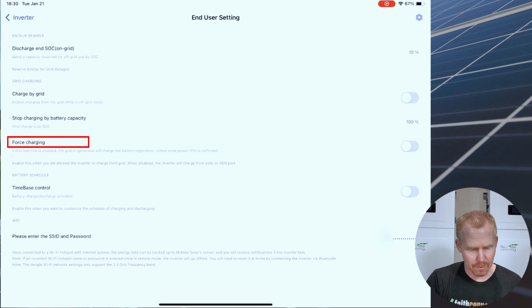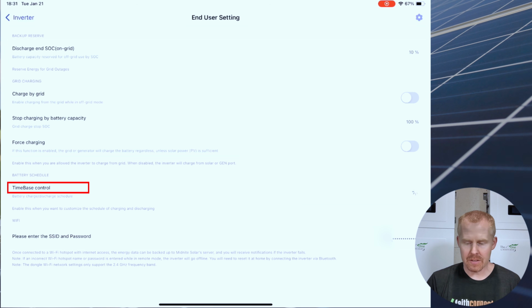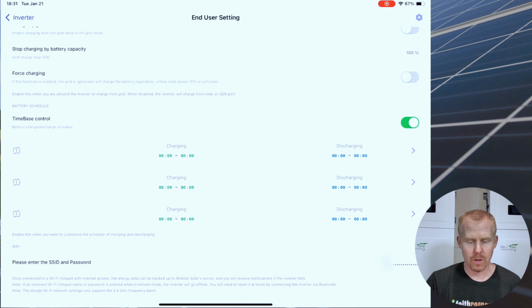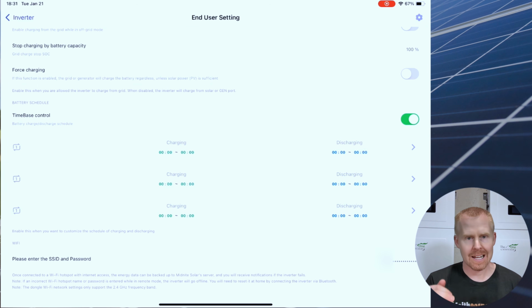If we look here, enable this when you allow the inverter to charge from the grid. When it's disabled, the inverter will charge from solar or the generator port. The time-based controls are going to give you 3 different time slots where you can tell the system that you want it to only charge or only discharge. I believe this is more for a grid connected feature, where it's going to try and discharge the batteries and actually push power back up through the grid.